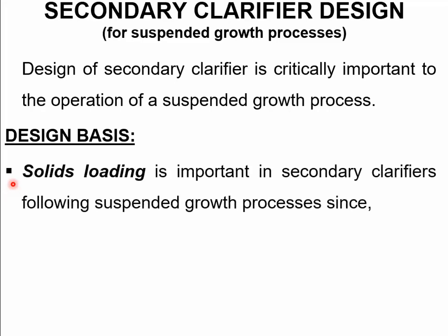So design basis for a secondary clarifier is not similar to the design basis for a primary clarifier. In primary clarifier, since discrete particle settling or flocculant particle settling is encountered, design of primary clarifier is a bit different, whereas in secondary clarifier, hindered settling, type 3 settling of particles occurs, therefore its design basis is different. The design basis for secondary clarifier is solids loading rate.